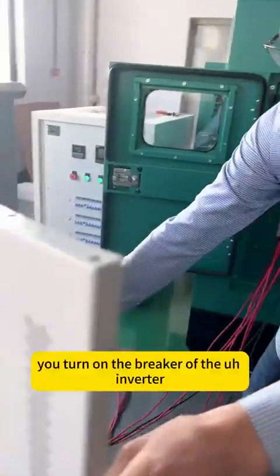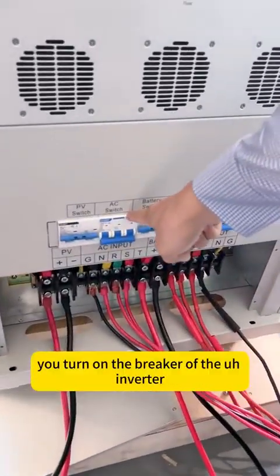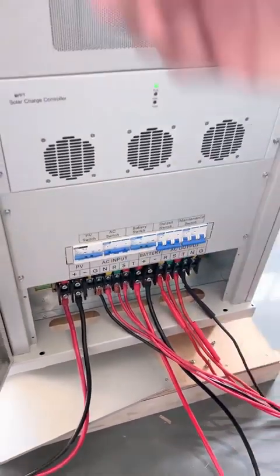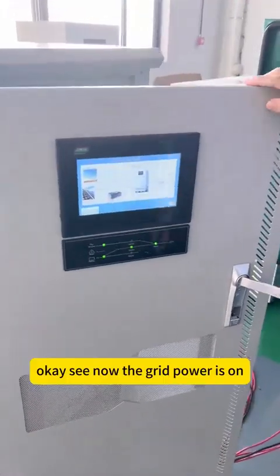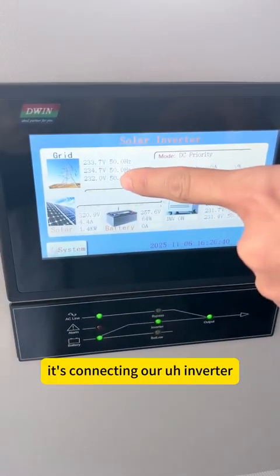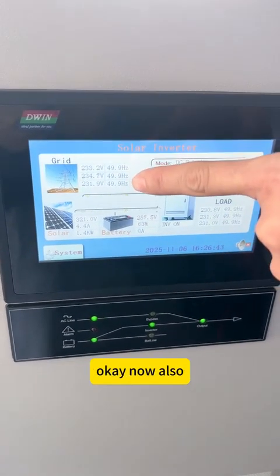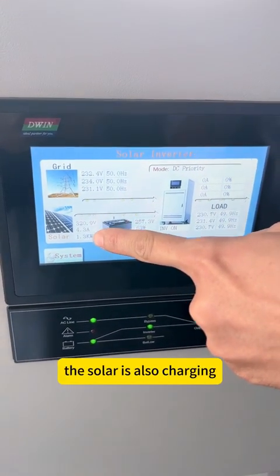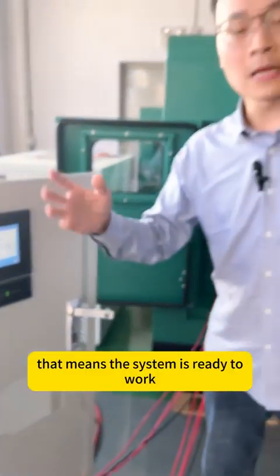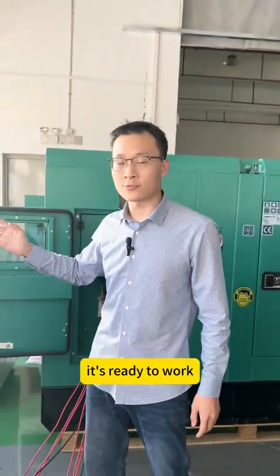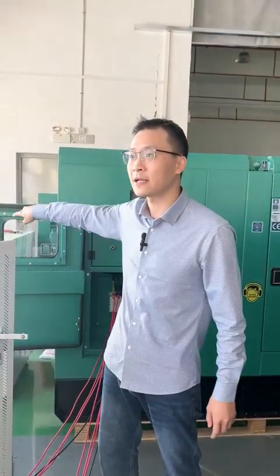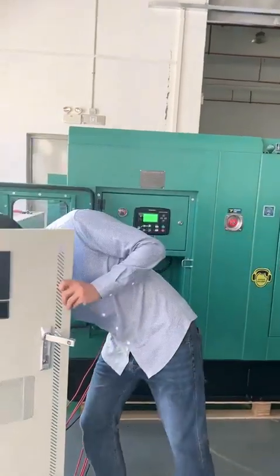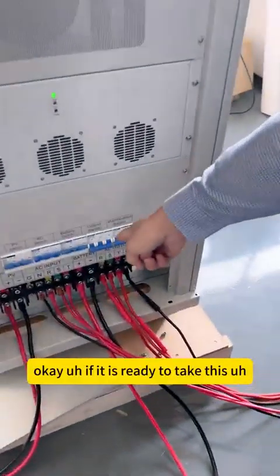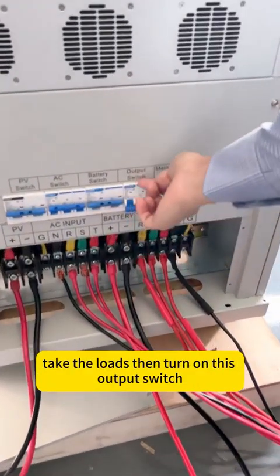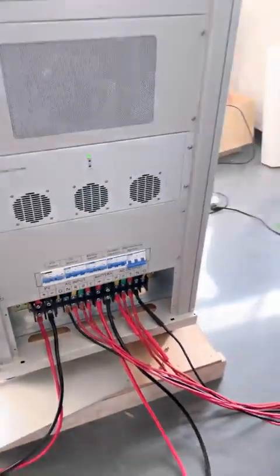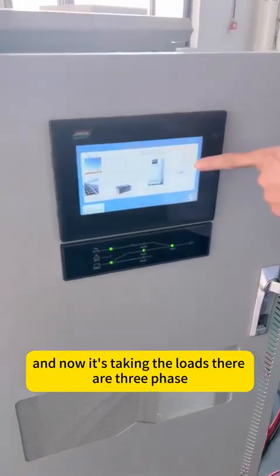you turn on the breaker. Turn on the breaker of the inverter. This is the AC switch. Now the grid power is on. It's connecting to our inverter. Now the solar is also charging. That means the system is ready to work. Let's start to take the loads. If it is ready to take the loads, then turn on this output switch. Now it's taking the loads.